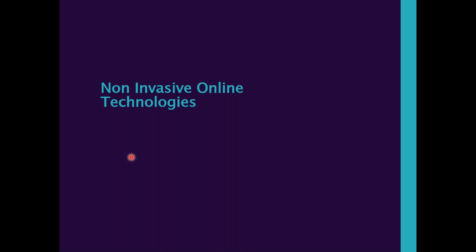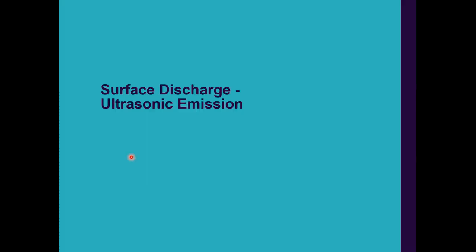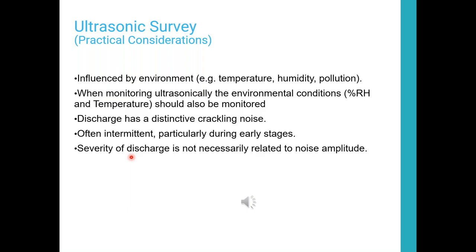So now we'll compare them to non-invasive or online tests. Surface discharge, as we said earlier, is ultrasonic. Now, you will be able to detect surface discharge with the VLF test set. You'll see the conducting of that carbon, of the arcing. You'll be able to detect it. Maybe a little different setup where you're going on a bus bar versus the switchgear ground point. But it can be detected. You can put the voltage up and you can get the activity going.